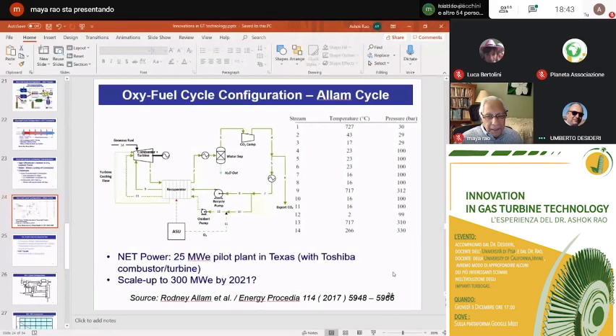Most of the work we've done using oxygen as fuel, in oxy-combustion, limited the oxygen, as I recall—this was with preheated oxygen. I'll have to look up the temperature we used for oxy-combustion; this wasn't in gas turbine cycles but in a boiler plant. We went as high as 60% oxygen, with the rest mostly CO2. But there's a corresponding temperature to each oxygen partial pressure, and I don't recall the exact temperature offhand.